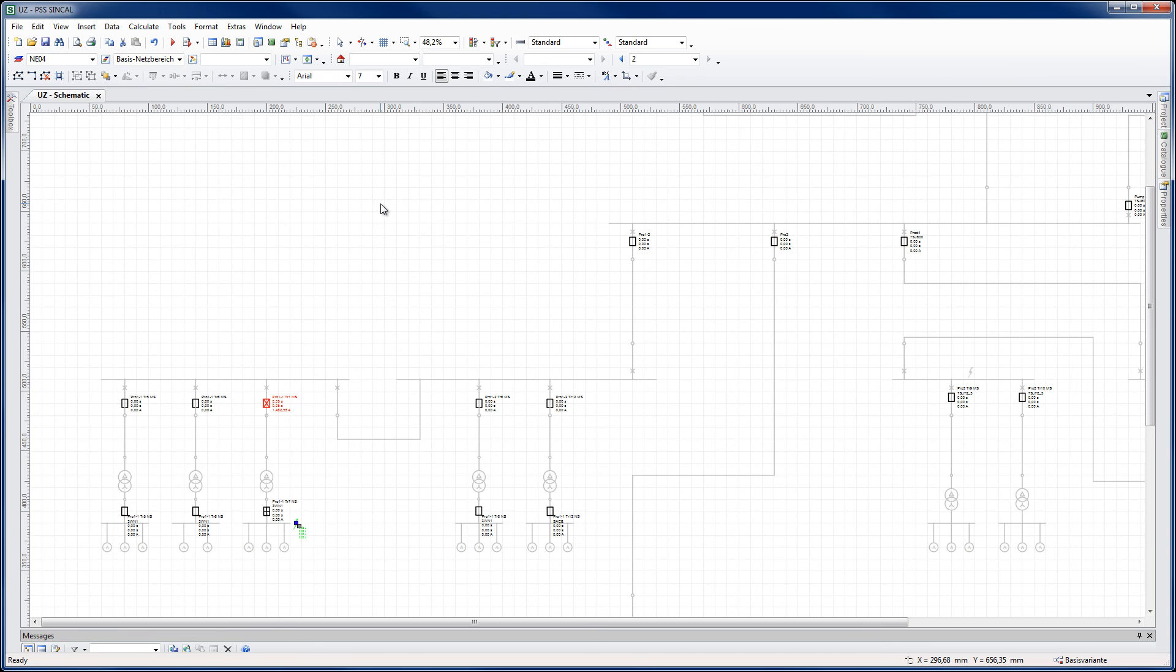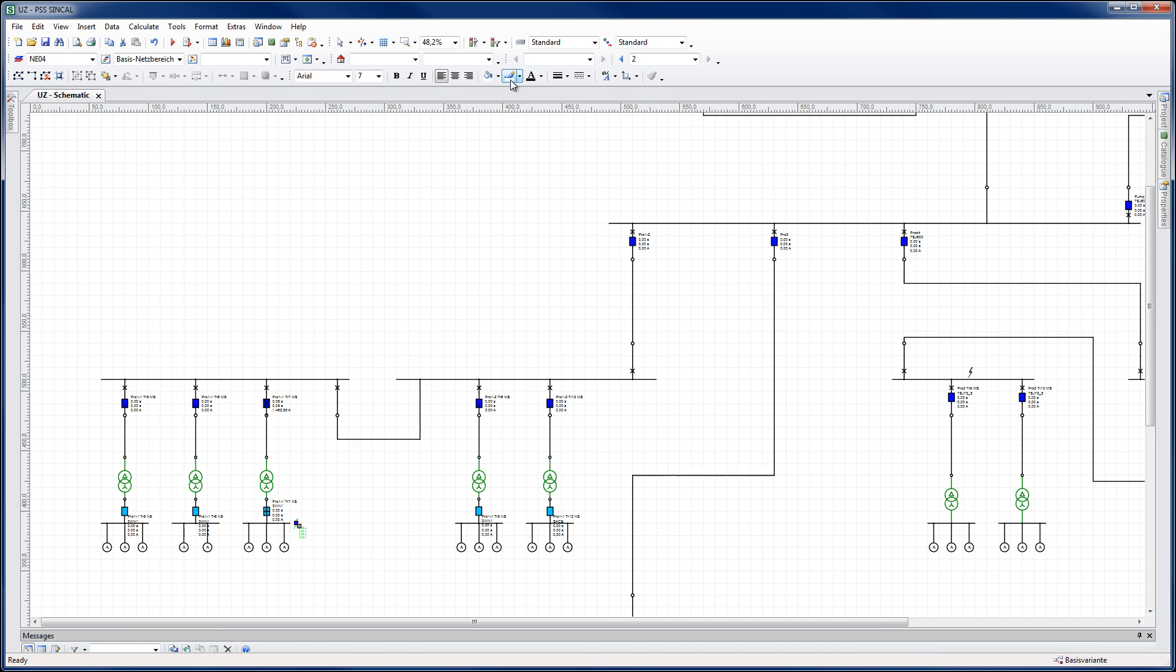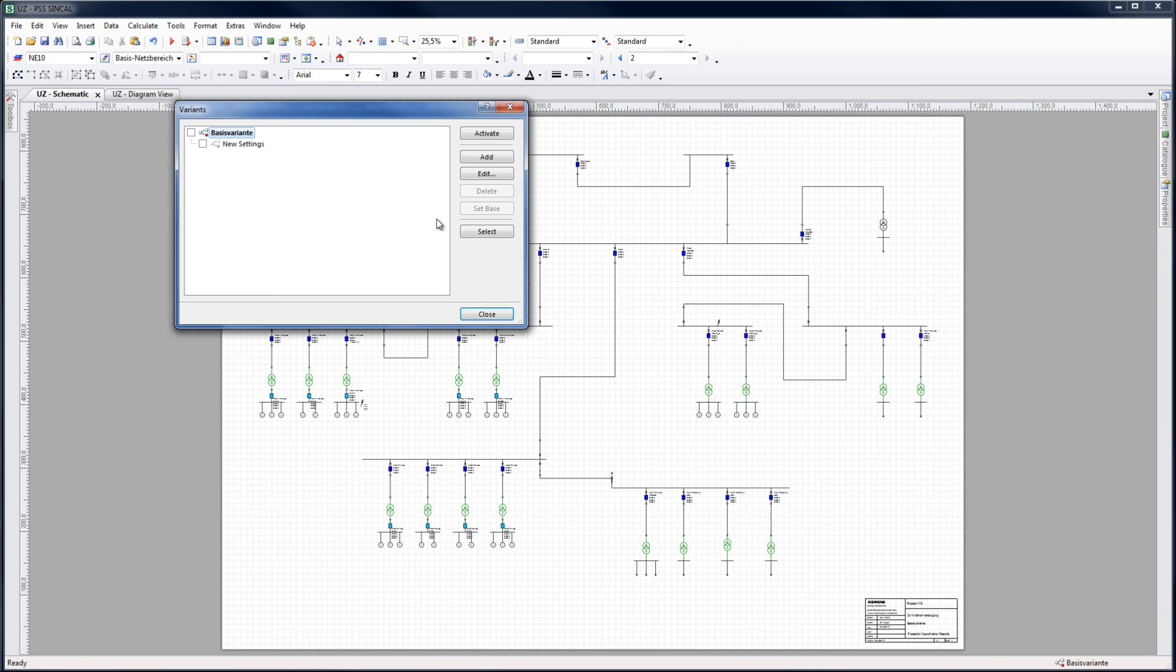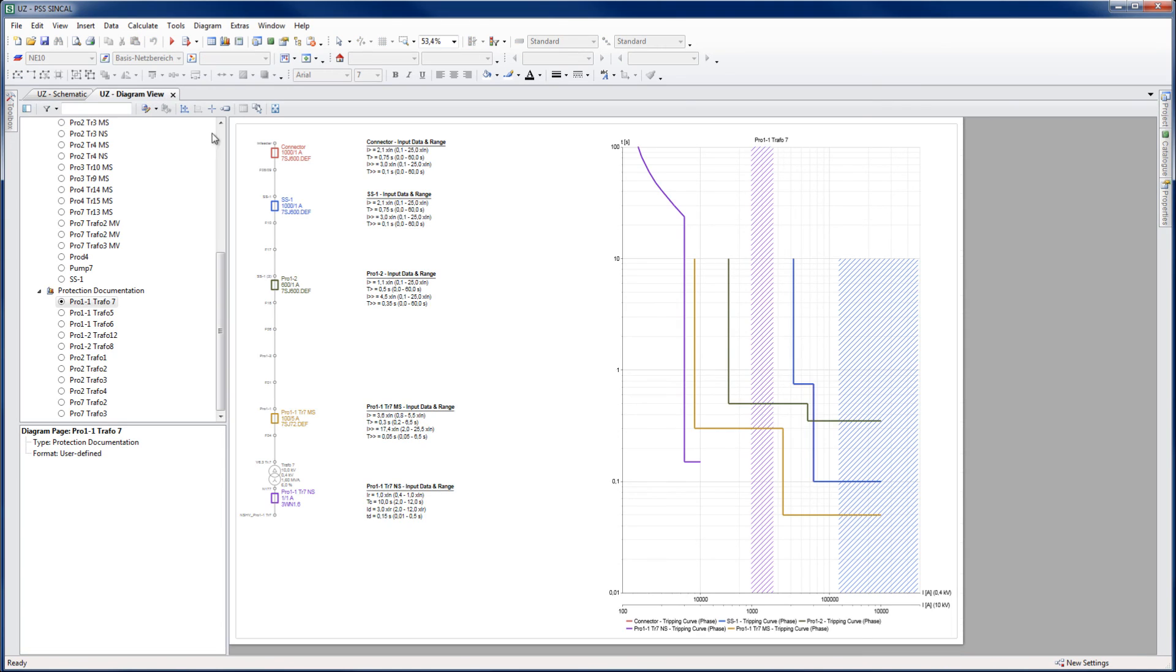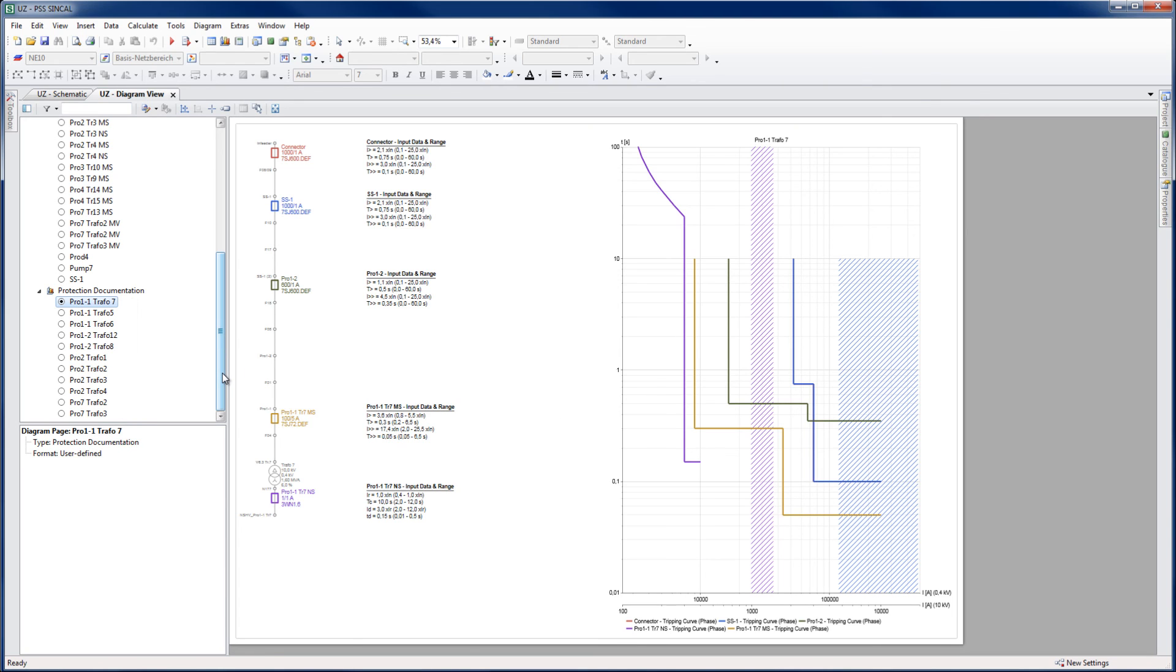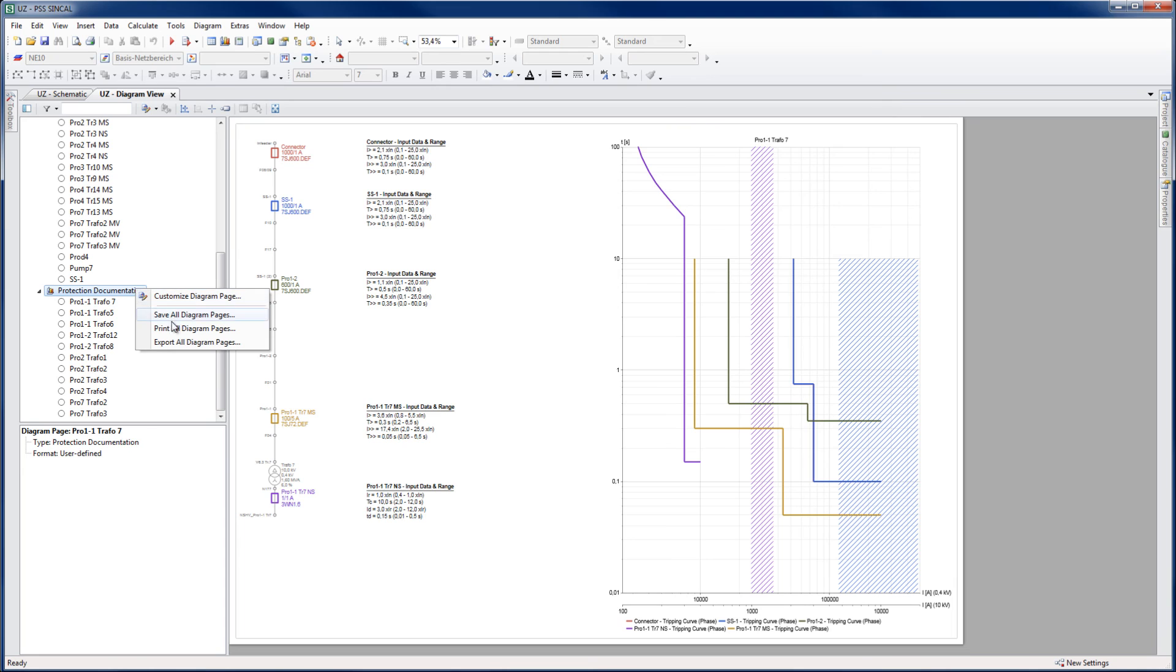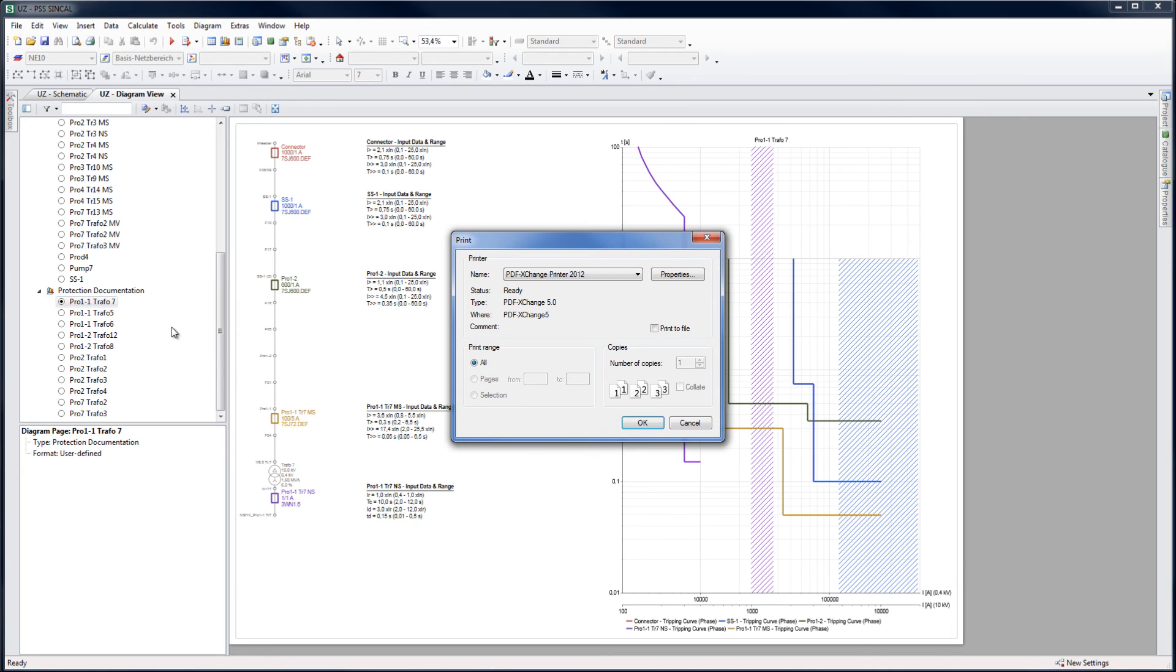To make new improved settings without losing the current settings, create a new variant. From the grading diagram, it can be seen that the new settings are well coordinated. This behavior could be verified again in the simulation environment if needed. And this process can be repeated for all protection routes in the network. Once the protection settings have been finalized, the protection documentation can easily be printed to provide a comprehensive end documentation.